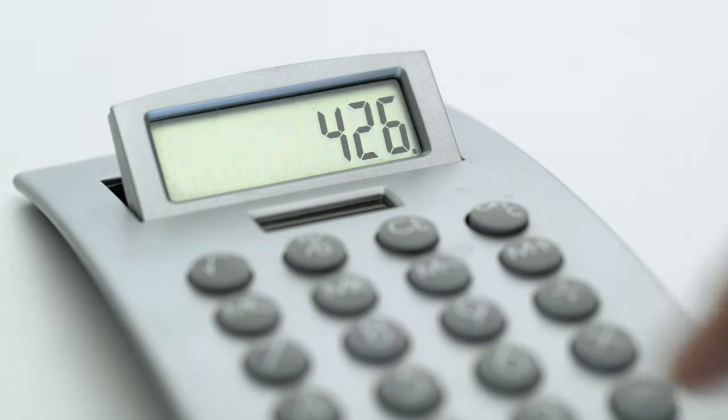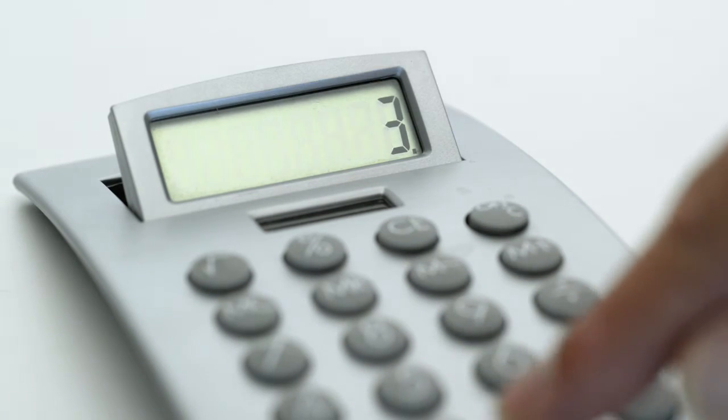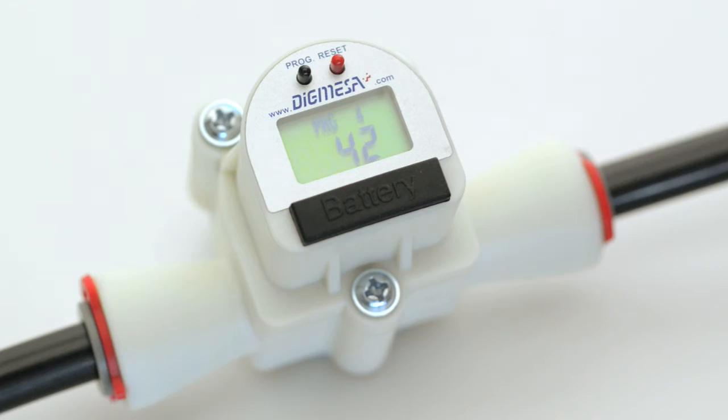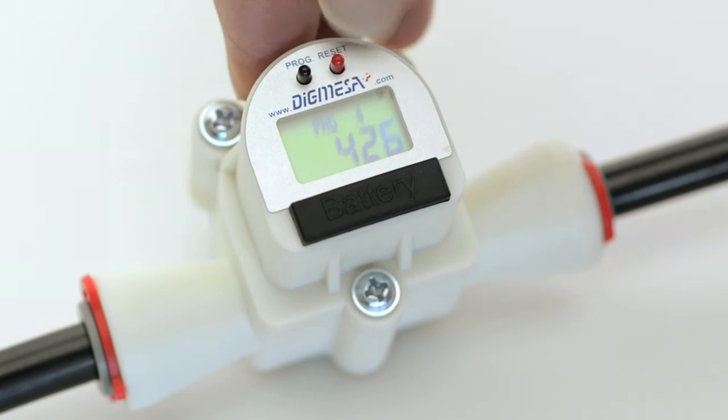Now convert into gallons. 426 times 3.78 equals 1610. This is your impulse count per gallon, which you can now program in as previously shown.